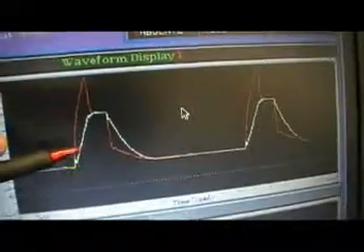The ventilator, going through our circuit, is delivering those breaths to our patient. The flow comes back through our passive humidity device, through our connector. I'm measuring the pressures on the patient's side — these are actually the mouth pressures. Then we're going through a resistor, which mimics the endotracheal tube. It's got a resistance of 20. We're going to measure the pressures on the other side, which are reflective of the alveolar pressures actually delivered in the patient's lungs. The red line on the graph indicates the mouth pressures — the pressures you would see on the ventilator waveforms. The white line represents the measured lung pressures within the lung.